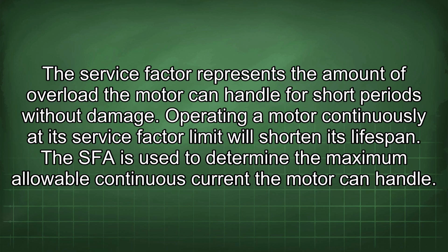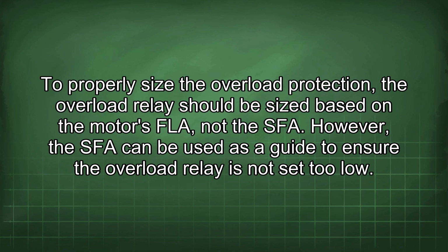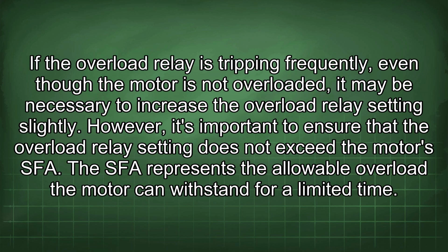The SFA is used to determine the maximum allowable continuous current the motor can handle. To properly size the overload protection, the overload relay should be sized based on the motor's FLA, not the SFA. However, the SFA can be used as a guide to ensure the overload relay is not set too low. If the overload relay is tripping frequently, even though the motor is not overloaded, it may be necessary to increase the overload relay setting slightly. However, it's important to ensure that the overload relay setting does not exceed the motor's SFA.